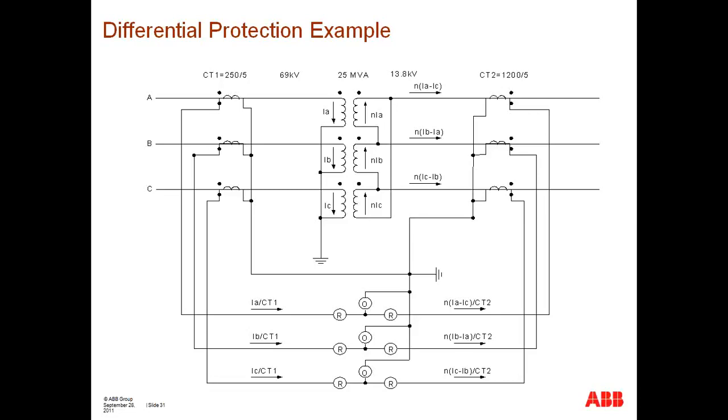And this high rise of pressure is not so much a function of the magnitude of current, but a function of arcing, the composition of oil, and gases being released inside the tank of the transformer as a result of that arcing. So yes, indeed, if the through fault stresses the insulation inside of the transformer in such a way that it evolves into an internal fault of the transformer, then your SPR is going to operate.